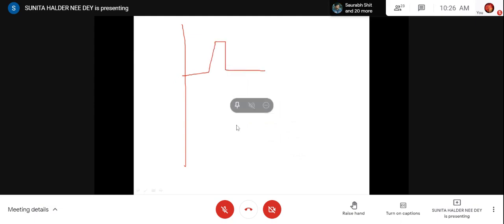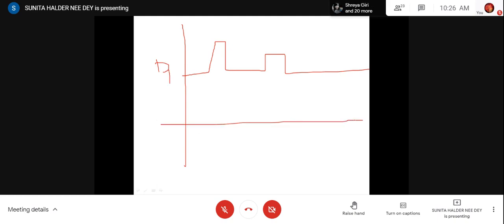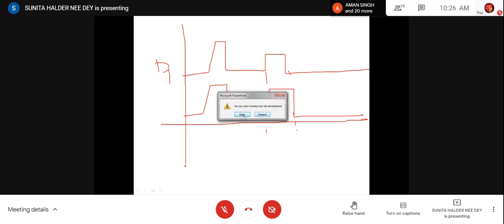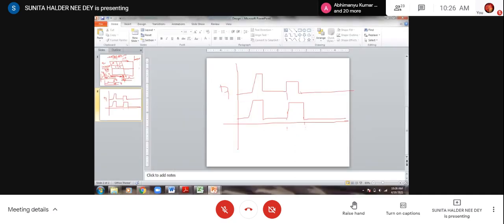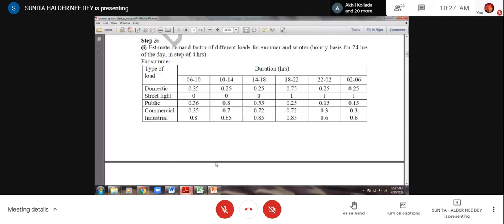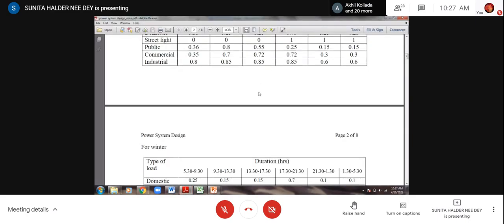just here, if you see that the load curve of each sub block is the same. So you are drawing the load curve for each sub block. This is for D1, say. For D2, you just draw it. If it is coming the same, or maximum demand is coming at the same position, that means the distribution of load is taken in a better way. So that's why it is important to give the load curve. But now we should not give it. You give it when you submit the final report. Why is it not required?